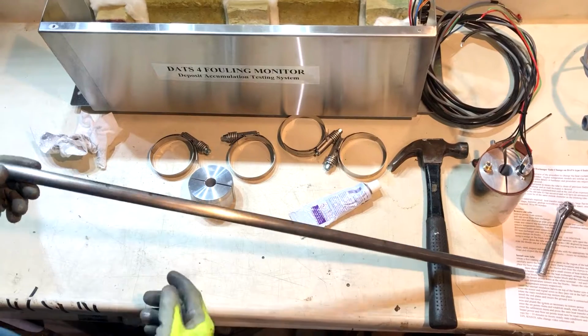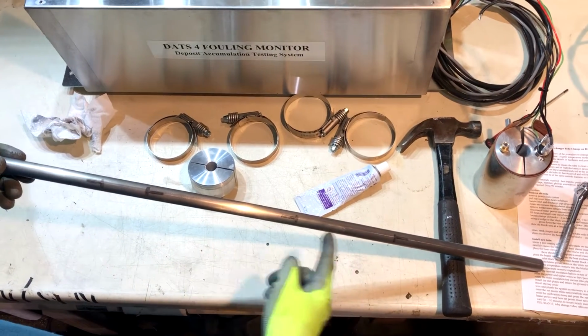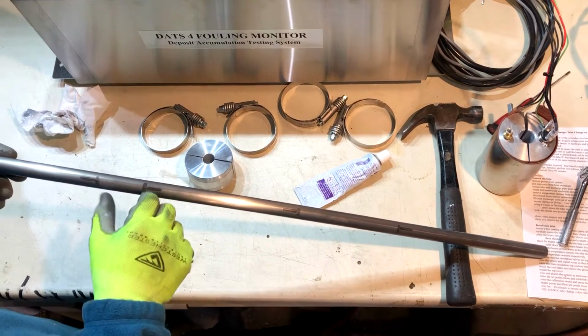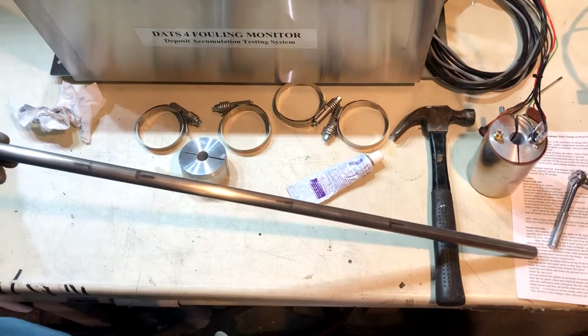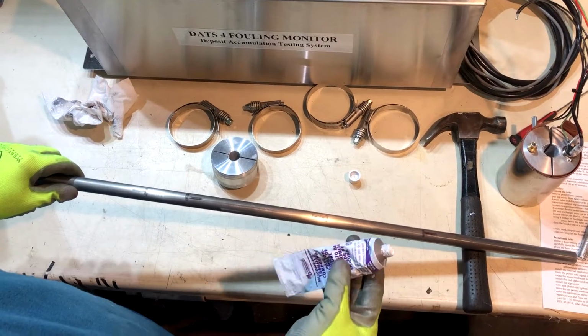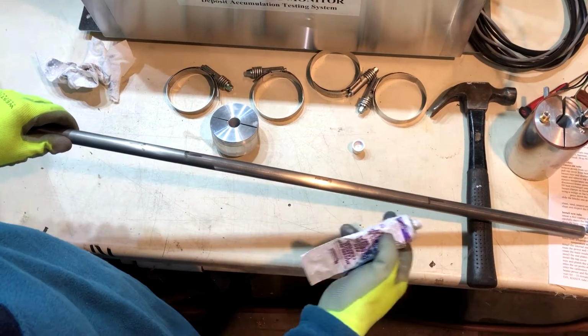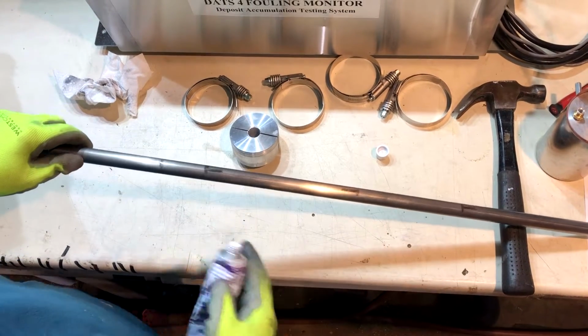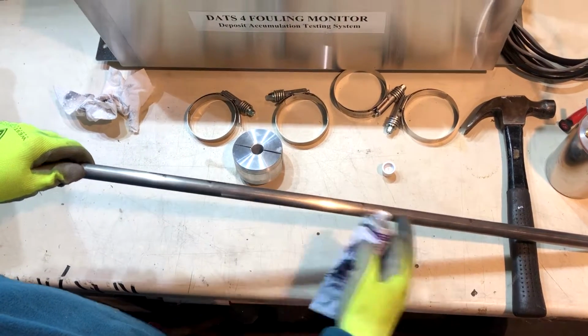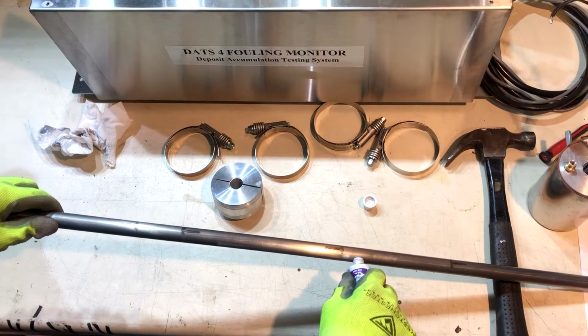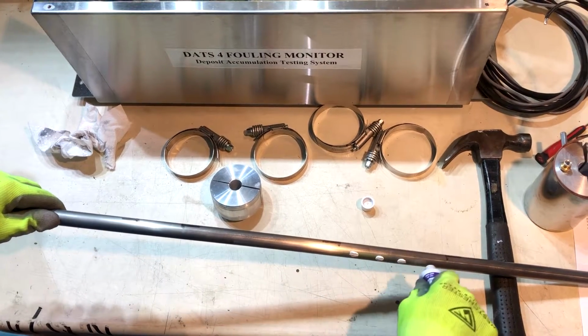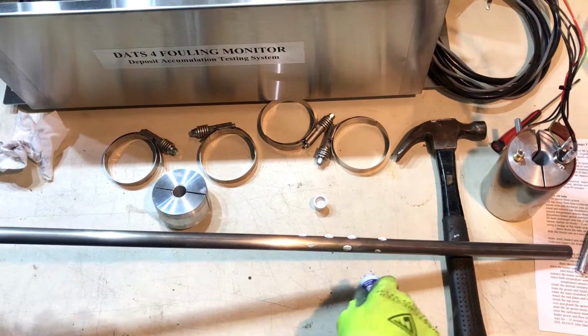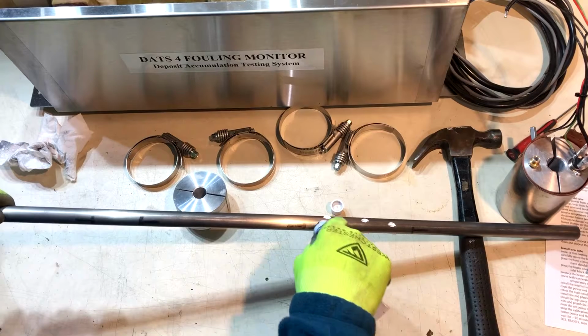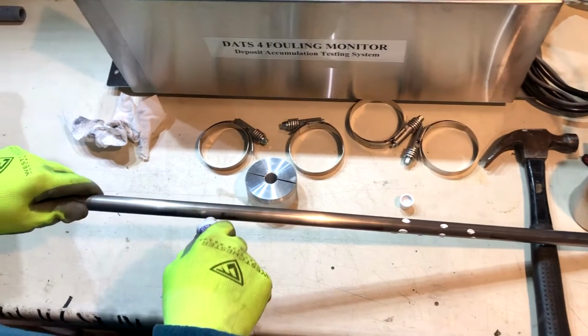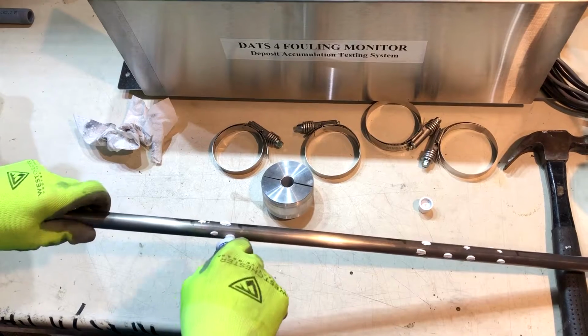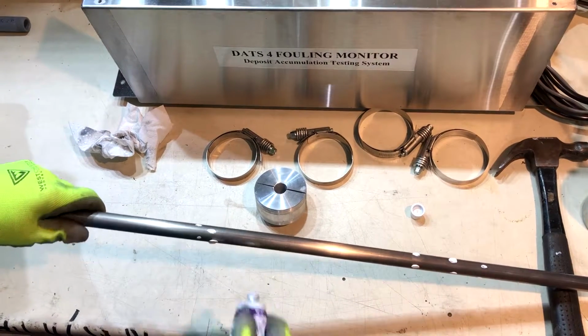Okay, so if you've purchased your spare heat exchanger tube from Bridger Scientific, it should be pre-marked with the locations of the heater block and the inlet block, roughly, so that they fit in the insulation that's already been cut. Okay, the next step is to use your heat transfer paste and smear it on the exterior of the tube. This tube has already been sanded smooth and any burrs removed. So only a small quantity of this heat transfer paste is required here, and applied judiciously, we remove any extra off. The heater block is the most important component, but the inlet block also requires it for more intimate surface.